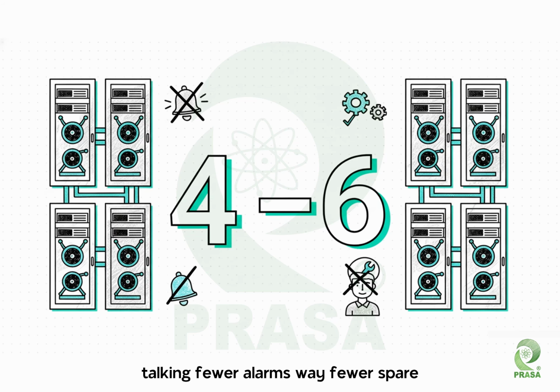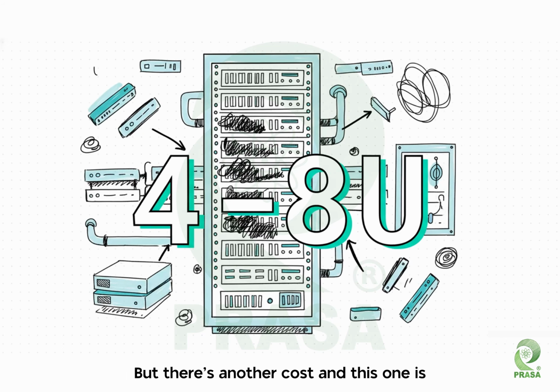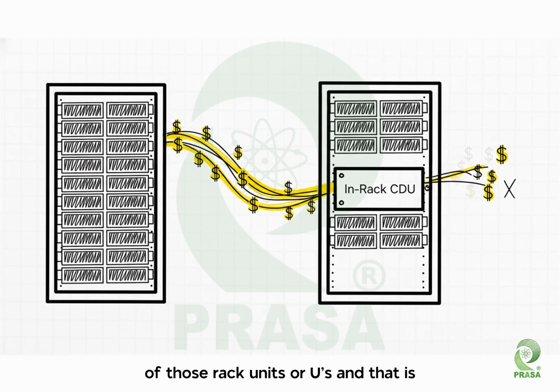We're talking fewer alarms, way fewer spare parts to keep in stock, and a dramatically lower risk of somebody making a mistake during maintenance. But there's another cost, and this one is a really big one: physical space. Every single one of those in-rack CDUs eats up valuable real estate inside the server rack. We're talking anywhere from 4 to 8 of those rack units, or Us. And that is not just empty space. In the world of high-density AI, every single U of rack space is potential revenue. By putting your cooling infrastructure inside the money-making space, you are directly sacrificing compute density. You're sacrificing your ability to generate income from that footprint. It's a business trade-off that, frankly, makes almost no sense.